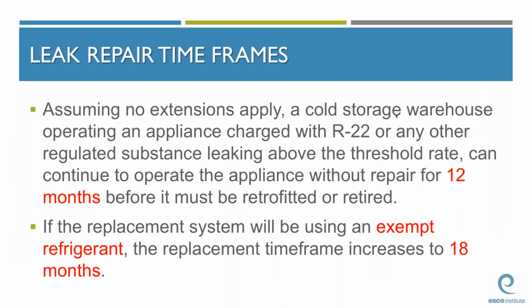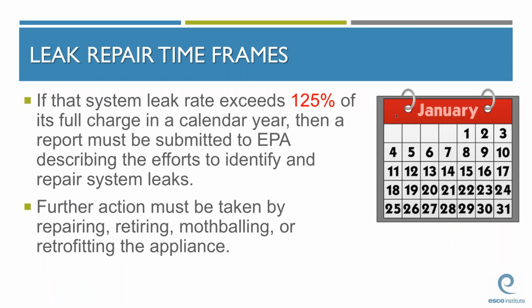If the annual leak rate on a system containing more than 50 pounds of regulated refrigerant continues to be in violation, even after repair attempts have been made, the system must be either retrofitted or retired. The retrofitting or retirement process must be completed within 12 months. And during this 12-month period, this leaking system can remain in operation. If this leaking system is going to be replaced with one that uses an exempt refrigerant, the equipment owner has 18 months to retire that system. If a system's annual leak rate exceeds 125% of the total refrigerant charge, a repair, retrofit, retire, or replacement plan must be submitted to the EPA.